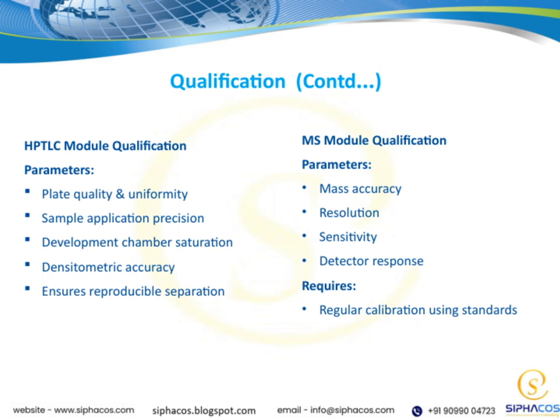We need to pay close attention to plate quality and uniformity, as these affect separation consistency. Sample application precision is also vital to ensure our samples are applied consistently. Development chamber saturation must be monitored to maintain proper development conditions. Lastly, densitometric accuracy is critical for quantitative analysis. Collectively, these parameters ensure that our separation process is reproducible and trustworthy.